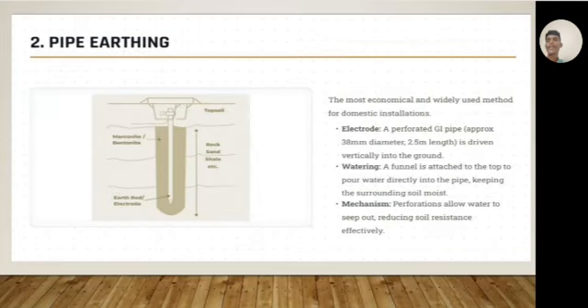Second point, pipe earthing. Pipe earthing is the most economical and widely used method for domestic installations. First point, electrode. A perforated galvanized iron pipe, 38 millimeters in diameter, is driven vertically into the ground. Second point, watering. A funnel is attached to the top to pour water directly into the pipe to keep the surrounding soil moist.